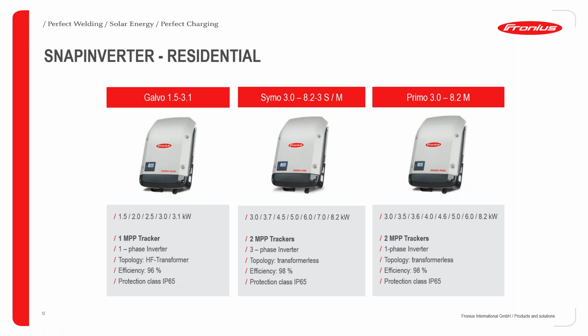So you can check that up to see the characteristics of IP65. But basically, just to give you a brief overview of the IP65 class, it can be installed outdoors because it is protected against dust and of course protected against jet water. By jet water, I mean it can be installed outside, even under the rain, and you can be assured that you won't have any ingress of water particles into the inverter.